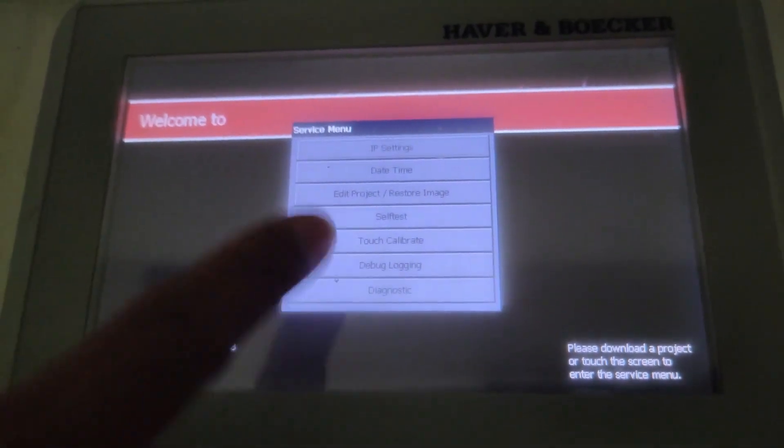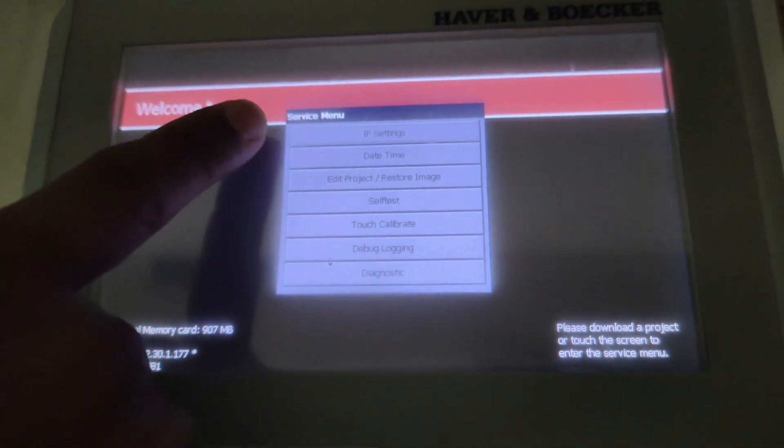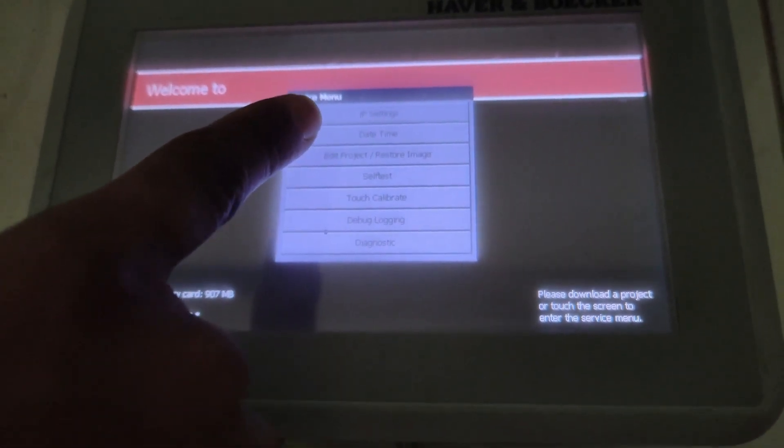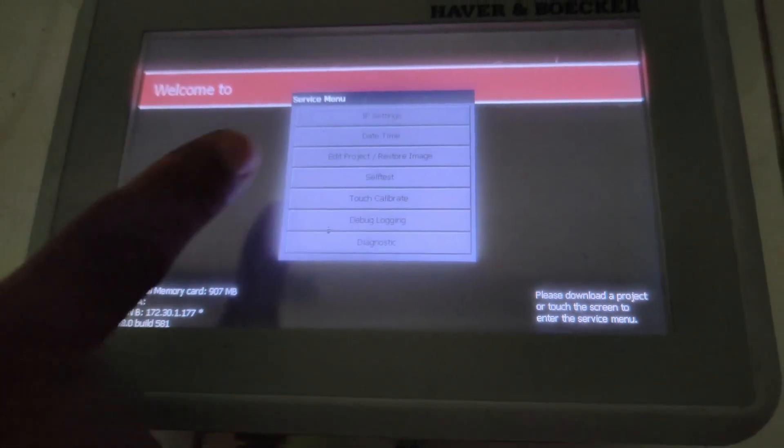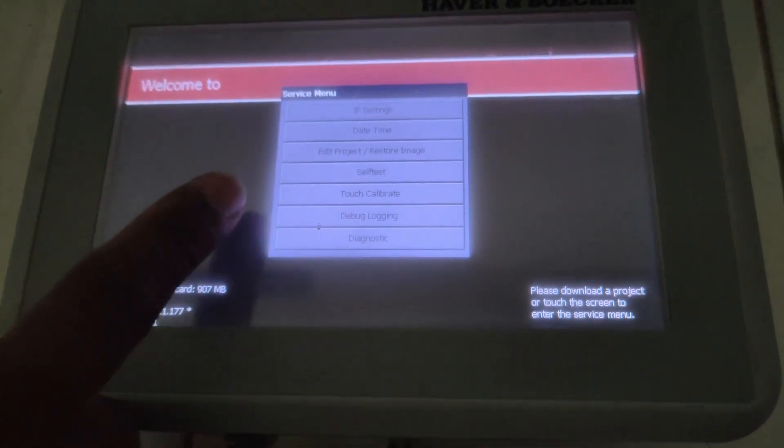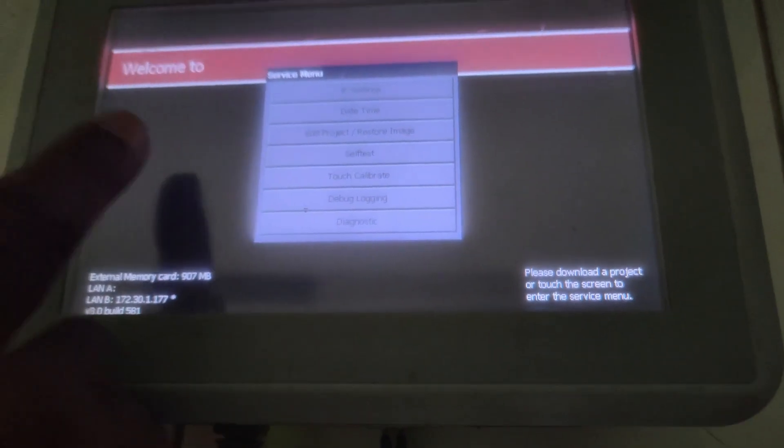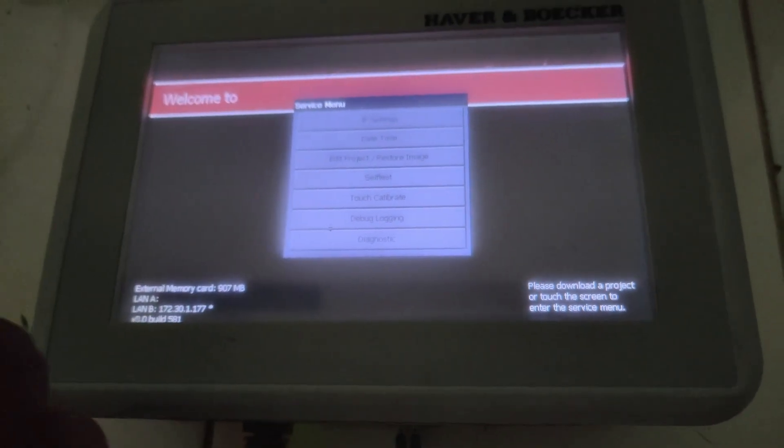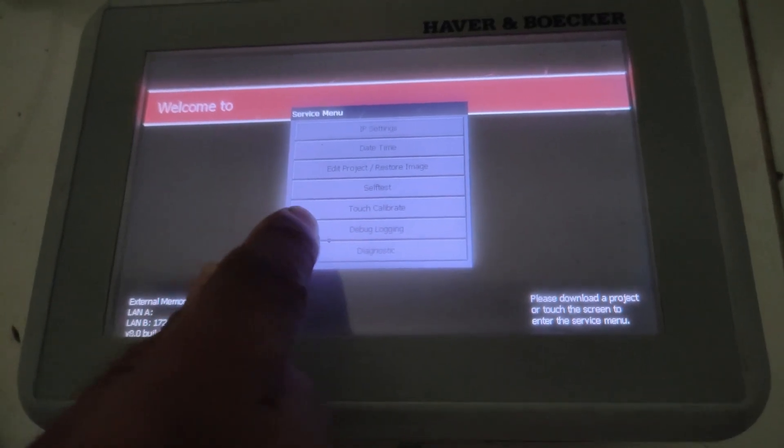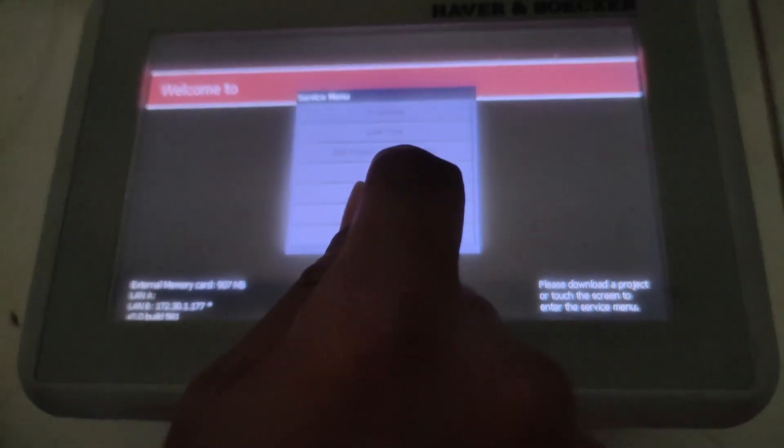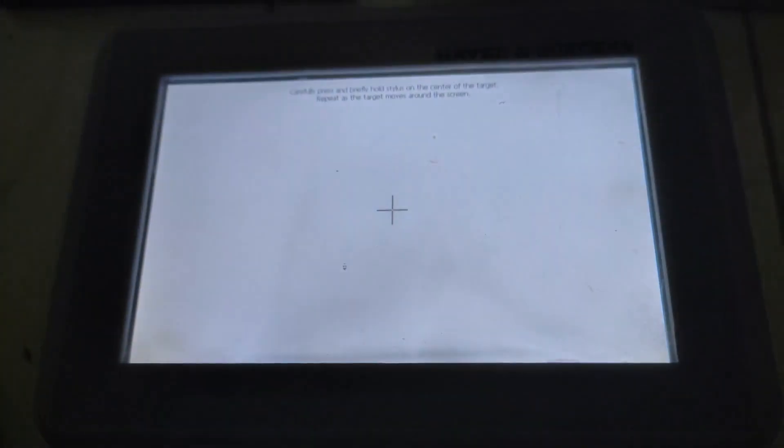From here you can set IP address, time, restore, or edit project from the service menu. But today I will calibrate the touchscreen, so click on Touch. Now click the plus mark at the center of that plus mark.